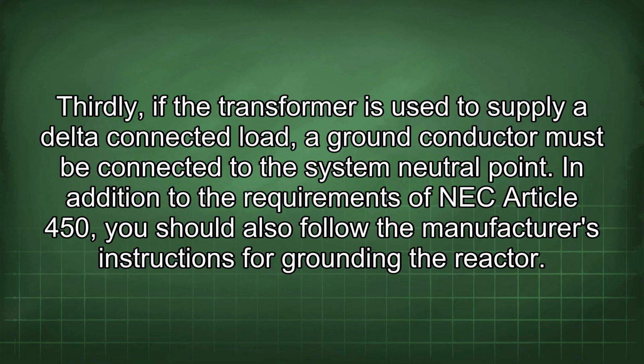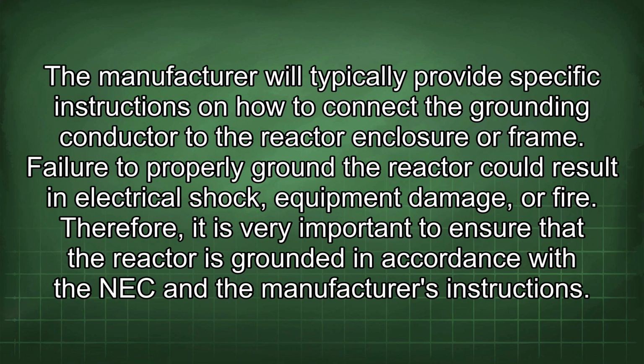Thirdly, if the transformer is used to supply a delta-connected load, a ground conductor must be connected to the system neutral point. In addition to the requirements of NEC Article 450, you should also follow the manufacturer's instructions for grounding the reactor. The manufacturer will typically provide specific instructions on how to connect the grounding conductor to the reactor enclosure or frame. Failure to properly ground the reactor could result in electrical shock, equipment damage, or fire. Therefore, it is very important to ensure that the reactor is grounded in accordance with the NEC and the manufacturer's instructions.